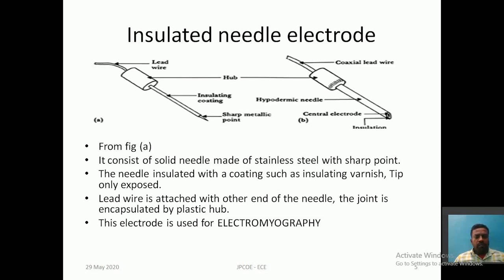So the insulated needle electrode consists of a solid needle made of stainless steel. First of all, it has a solid needle, see, this is a solid needle made of stainless steel with a sharp point. Then the needle is insulated by insulating varnish. Only the tip is exposed, that means the tip is not insulated and the remaining portion is insulated. That is one coating, by insulating varnish.